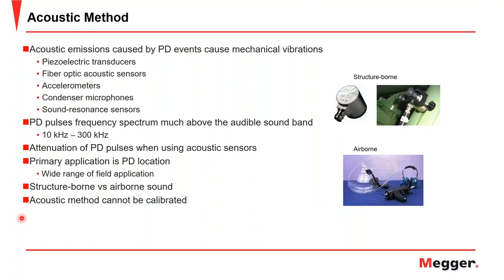And another big takeaway is similar to the electromagnetic method. The acoustic method cannot be calibrated as there is no correlation with the PD quantity, apparent charge, because a calibration of the acoustic method cannot be conducted to find a suitable reference value.